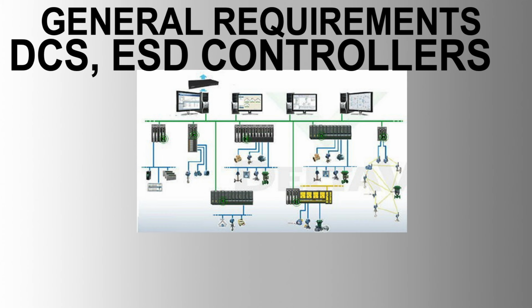5. Engineering workstations. Capabilities. Serve as configuration and programming consoles with all the capabilities of operator consoles. Redundant server with concurrent access to the configuration database for multiple clients. Capability to modify programs in any control interface, perform sequential programming, and configure regulatory loops. Security keys and passwords for access to engineering configuration data. Automatic backup of tunable controller configuration parameters, such as PID tuning parameters, high and low limits changes made by operators.